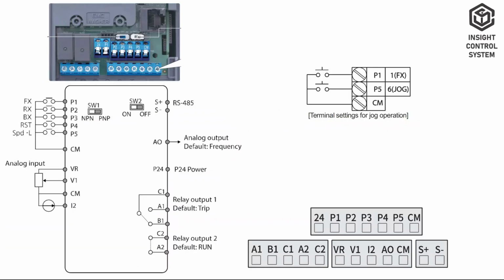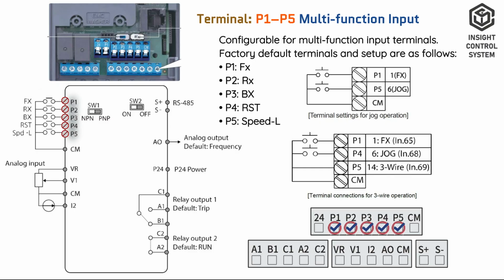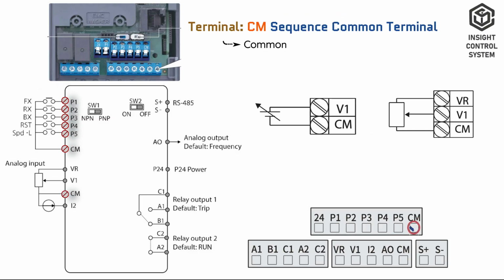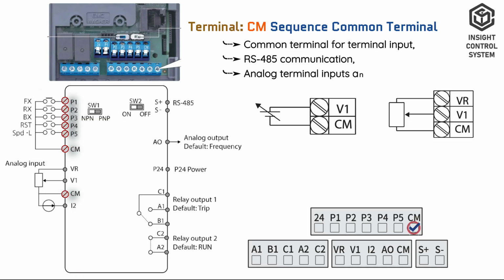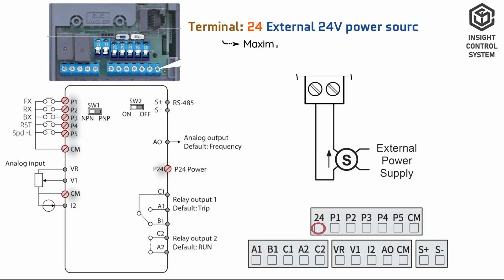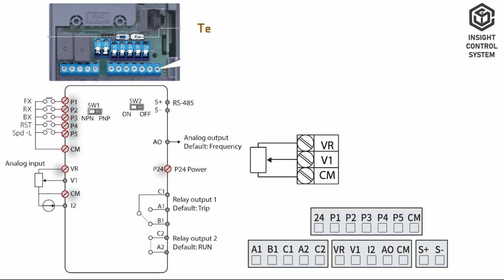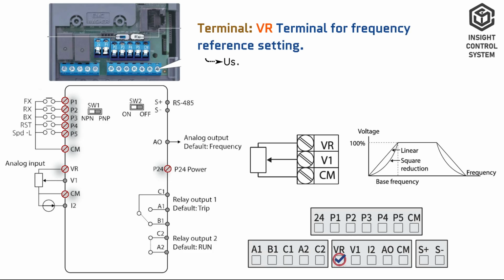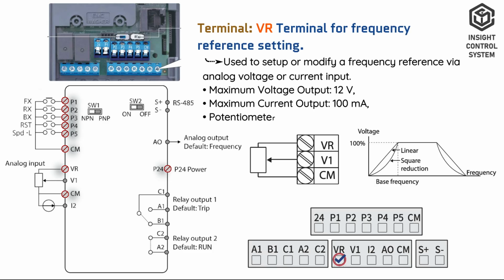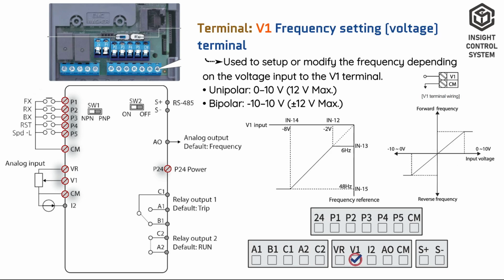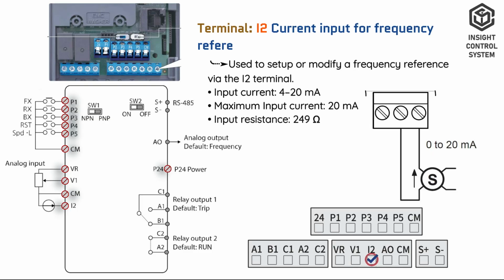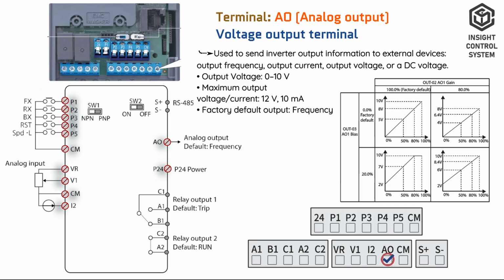Control terminals. P1 to P5 are configurable multifunction input terminals. CM is common terminal for terminal input, RS485 communication, and analog terminal inputs and outputs. 24 is external 24-volt power source. VR terminal for frequency reference setting, used to set up or modify a frequency reference via analog voltage or current input. V1 is frequency setting terminal for the voltage input. I2 is frequency reference input terminal for the current input. AO is analog output terminal that sends inverter output information to external devices.